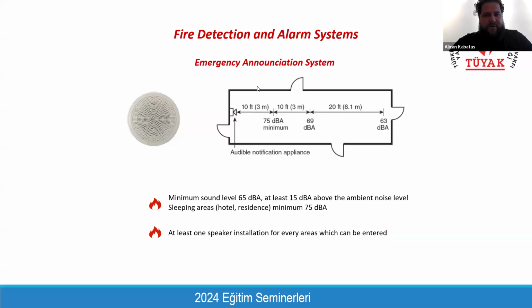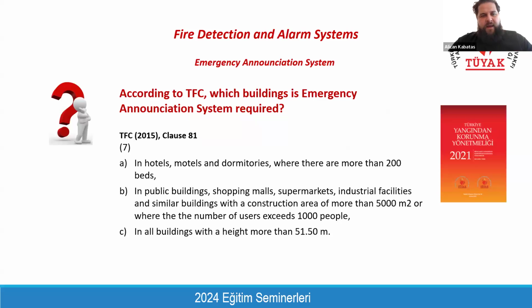And we will have an emergency announcement system. These are the speakers, and it is called public announce and voice alarm system. And we have some minimum sound level requirements. That's why we should have at least one speaker in every room. It means locating speakers only at the common corridors or common areas will not solve the issue. We need to have speakers within every room, and the ceiling design and the ceiling coordination should be done accordingly.